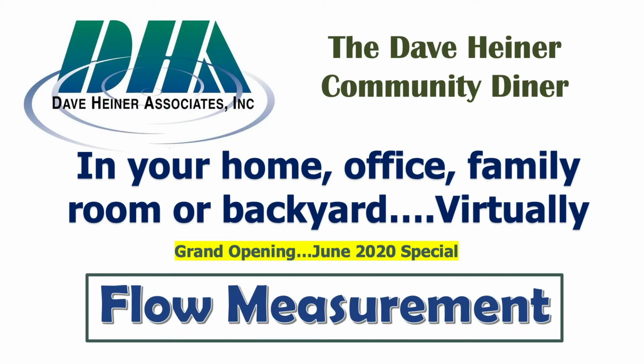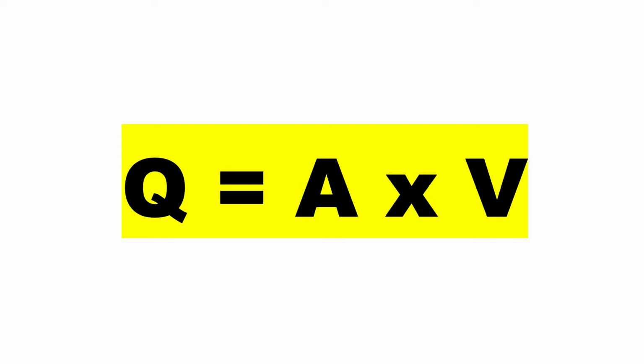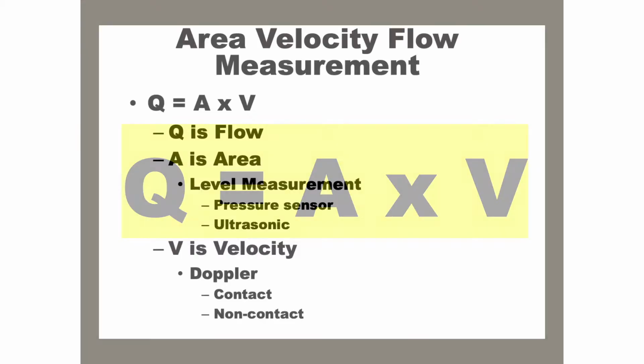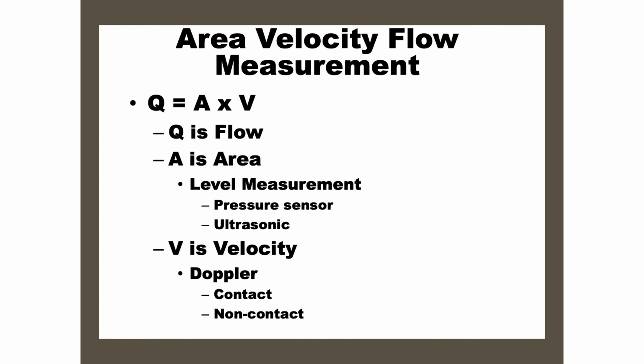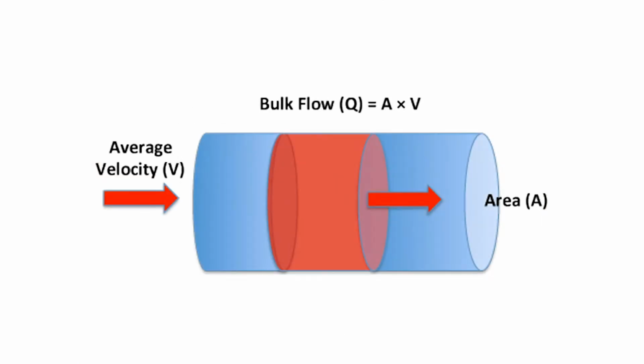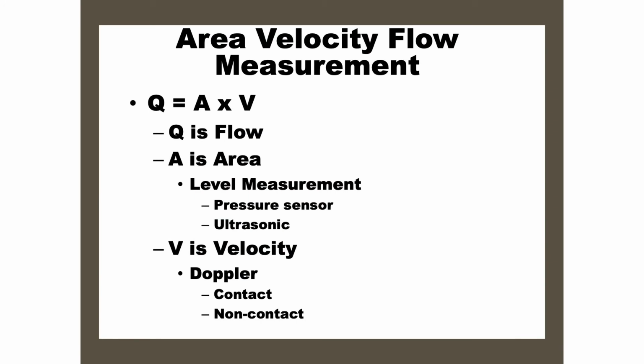First thing that you have to understand with flow measurement is the universal flow equation. In the universal flow equation, in which Q equals A times V, Q is flow. Q could be flow in millions of gallons per day, gallons per minute, liters per hour, whatever your increments of measurement are. A is area, and again, the area could be in square inches, it could be in square feet, whatever your measurement of area is. And V is velocity. And in our world, predominantly, velocity is feet per second.